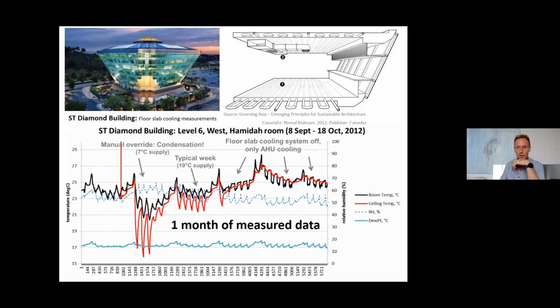And that means that the room temperature, which is the black one, you can see is actually getting a bit too high, because the whole system was designed to have both cooling coming from the floor slab and the normal aircon. So we're lucky to have some sensors measuring this. This happened about 2 years after the building was taken into use. So actually you get all those 3 situations: we have normal operation, we have the wrong operation where they cool it down too much, and then operation where there's no floor slab cooling working. So everything contained in one graph right there.